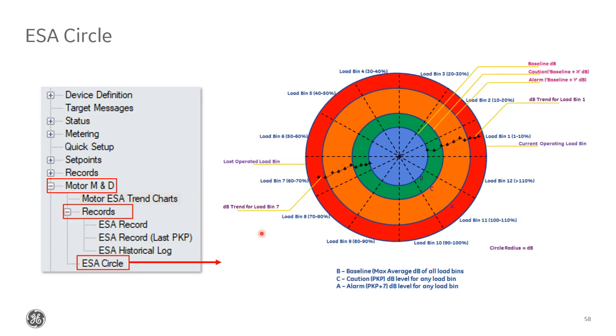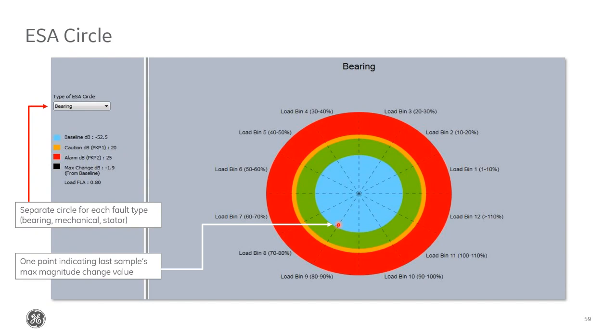And then the ESA circle, it's just an additional visual representation to make it a little bit easier for you to know if everything's okay or if the values seem to be trending outward. It's kind of similar to the trend charts that we provide now. It's just another way of showing what the values are. If everything's good, you'll see a dot representing the max change value in the blue or green area. If something's wrong, then you'll see the value trend towards the alarm area, and then you'll know something's wrong.